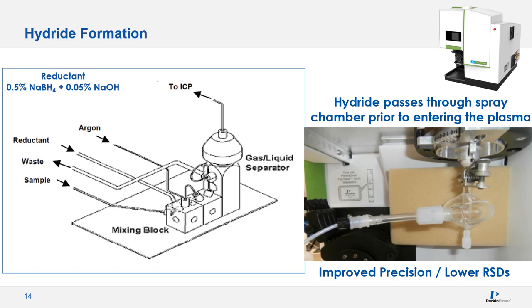One modification we made was passing the output of the gas-liquid separator through the spray chamber rather than directly to the ICP. This gave better precision — lower RSDs, less noisy signal, and ability to see lower levels. We did not observe any washout or carryover effects despite the gas phase species passing through the larger spray chamber volume. Implementation was simple: we cut a 5 cm piece of Tygon tubing from the normal nebulizer line and used an adapter to connect the GLS output into the spray chamber — no special tubing required.